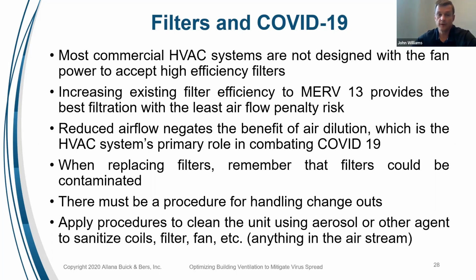First of all, they could be contaminated. We're talking about potentially capturing some of this virus in the filters. We need to be very careful, because when we send somebody up there, they need to have PPE. They need to have bags for the old filters. They can't just be slinging them around. And they should clean and disinfect the unit as part of that filter change out, because we could have bacteria and virus in other areas of the unit itself.